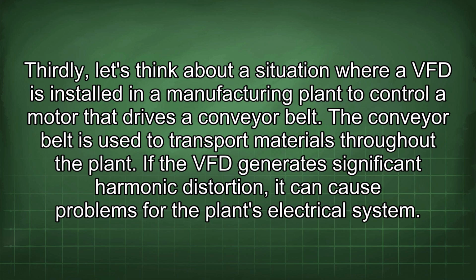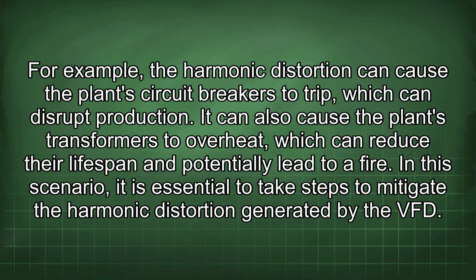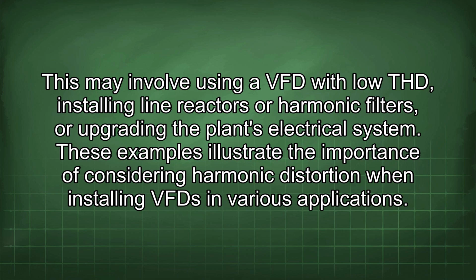Thirdly, let's think about the situation where a VFD is installed in a manufacturing plant to control a motor that drives a conveyor belt. The conveyor belt is used to transport materials throughout the plant. If the VFD generates significant harmonic distortion, it can cause problems for the plant's electrical system. For example, the harmonic distortion can cause the plant circuit breakers to trip, which can disrupt production. It can also cause the plant's transformers to overheat, which can reduce their lifespan and potentially lead to a fire. In this scenario, it is essential to take steps to mitigate the harmonic distortion generated by the VFD. This may involve using a VFD with low THD, installing line reactors or harmonic filters, or upgrading the plant's electrical system. These examples illustrate the importance of considering harmonic distortion when installing VFDs in various applications.